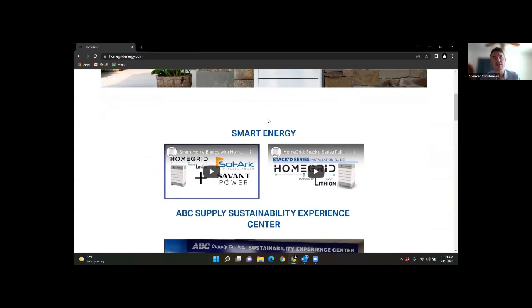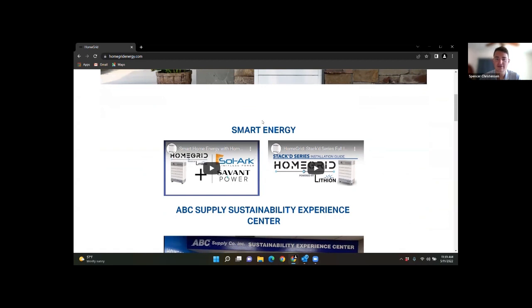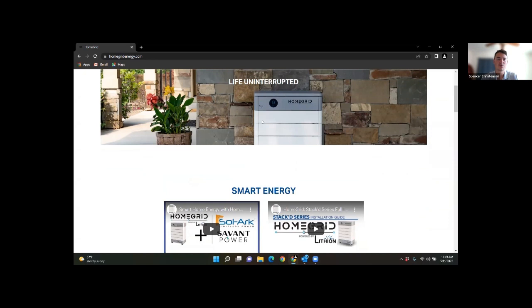The way this really works is that now we can eliminate the critical load panel — that's a big part of it. With the Sol-Ark 15K, it's got a 200 amp pass through, so you don't have to designate a couple of loads, which takes almost a full day to do with one of those critical load panels. You can just put your Sol-Ark on the system.